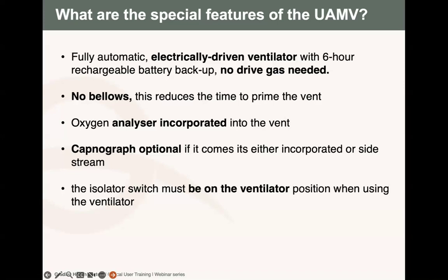And we don't have bellows. On the new ventilator, there's no bellow like on the previous ventilator, where we had a blue bellow on the side, which before starting ventilation, or before even connecting your patient, you first have to wait for it to prime until it's stable, and then you can connect your patient. With the new ventilator, there's no bellow. So that helps you in reduction of time if it's something that you need to start there. And then once you switch it on, you do the preliminaries, the FiO2 setup and all those things, you go straight, choose your mode, and then you can start ventilation.